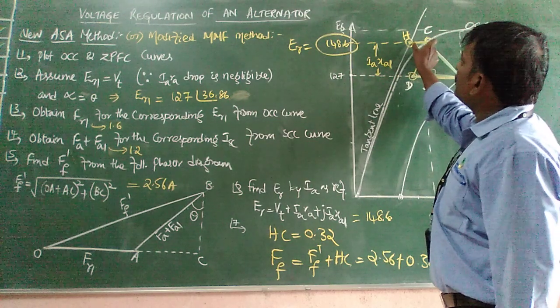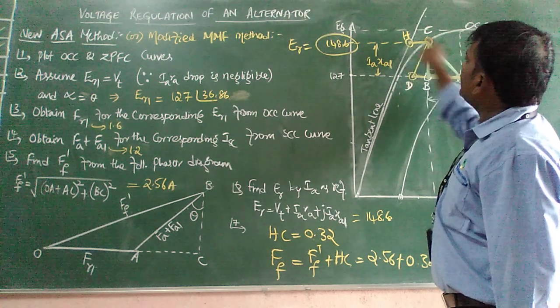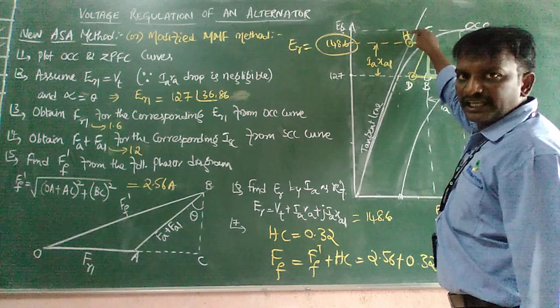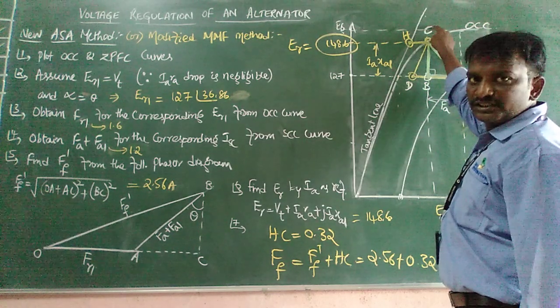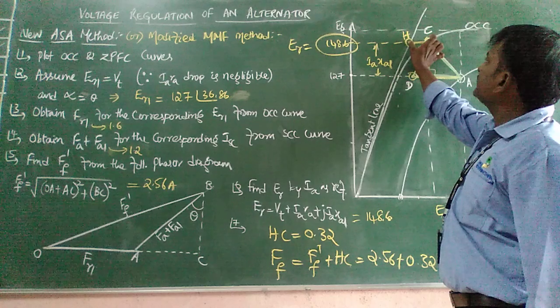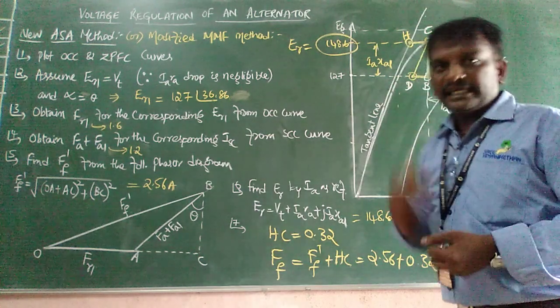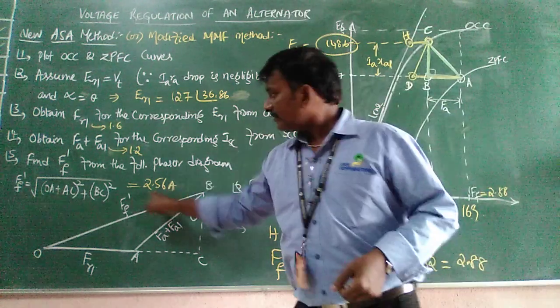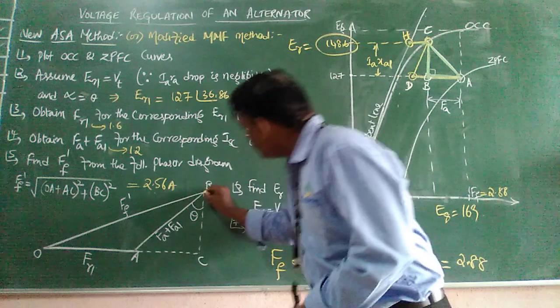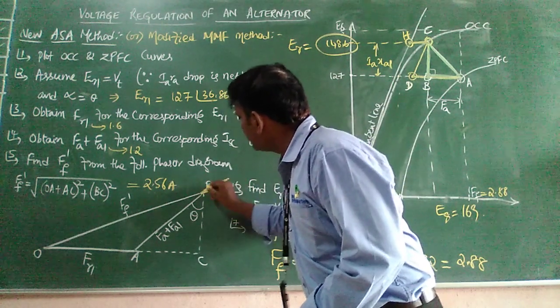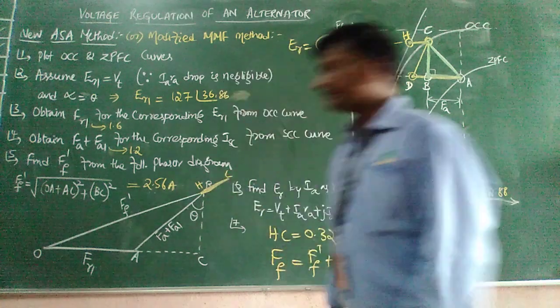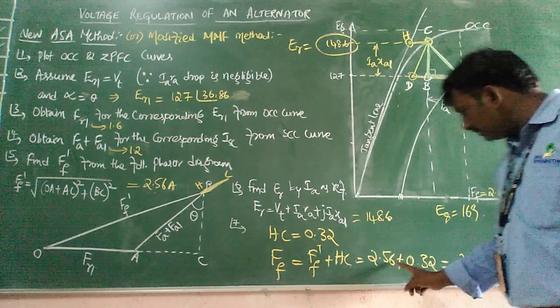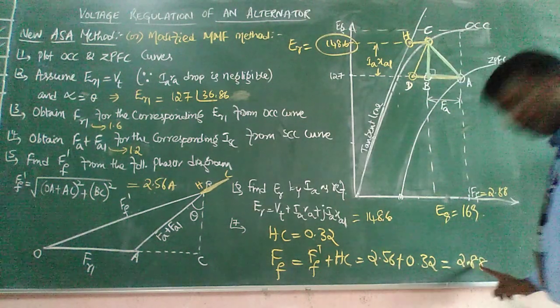Find out the distance between this tangent line and the OCC curve. In order to find the distance, consider H as the point on the tangent line and C as the point on the OCC curve. Find out the HC distance. That HC distance is the extra MMF required to add to FF dash to account for saturation. This length is your HC. So HC is added to FF dash — your entire value is 2.56 plus 0.32, giving you 2.88.